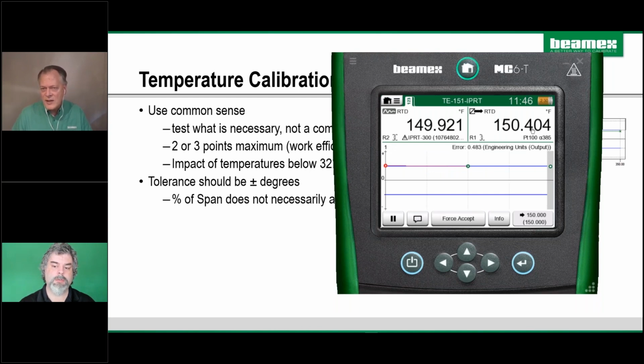As of today, it's reading 1/2 degree high, basically, compared to this nice reference probe measuring out to 3 decimal places. And regardless of what you're doing, this is an automated test. So however you're doing this, you should be using a system that you can press start and just walk away and let this work on its own.